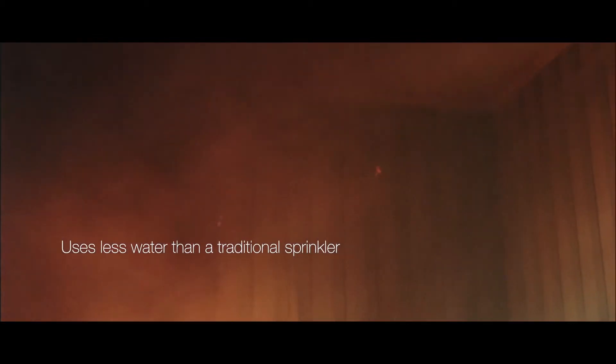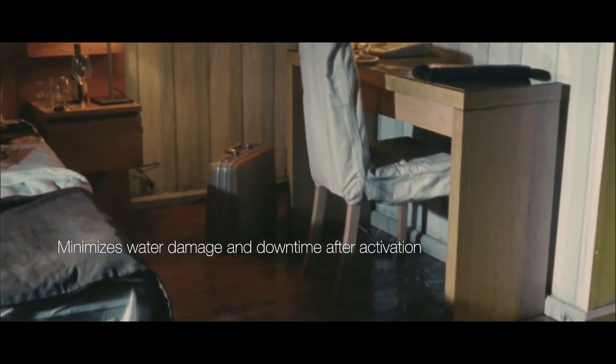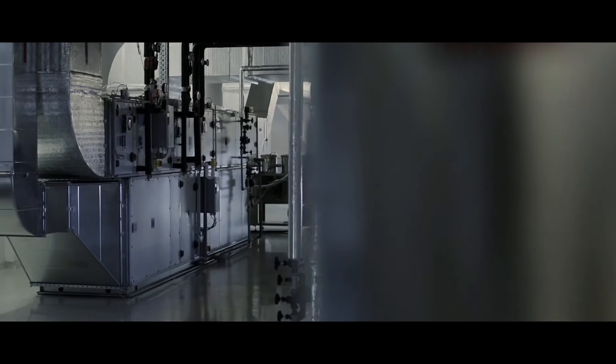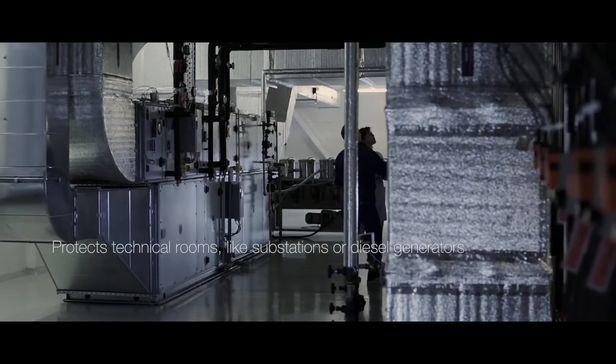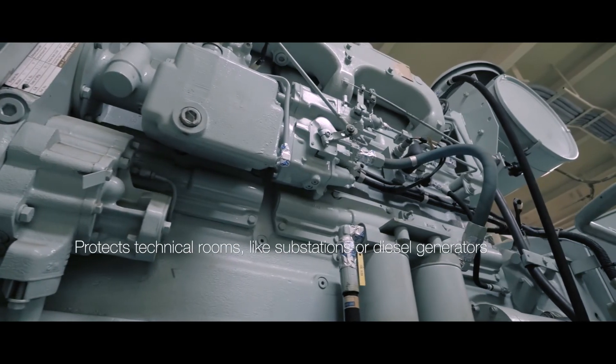On top of that, hi-fog uses significantly less water than traditional sprinklers, minimizing the water damage and downtime of your business after activation. Thanks to its versatility, hi-fog can also protect technical rooms like substations, UPS, or diesel generators.